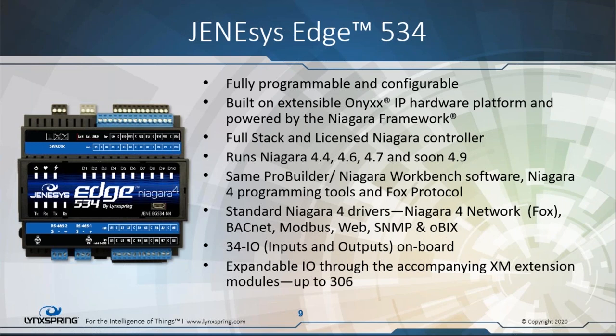Now this device specifically, because it is Niagara, because it is the full stack, supports all the open protocols, BACnet, Modbus. It has a web UI interface on board. It also has Niagara Fox, which we take advantage of extremely plentifully when deploying Edge devices. It has 34 I/O, and then like Marc was ending his dissertation on XMs, you can add enough XMs to get up to almost 306 points of physical IO. Of course, that's always limited by your global capacity license in the Niagara world.